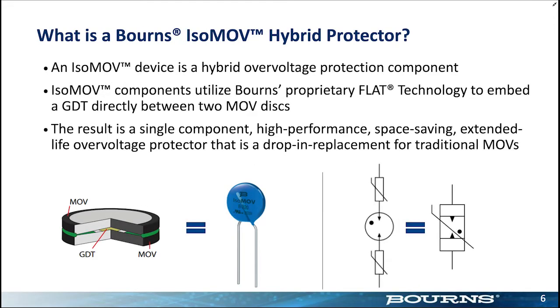So what is this IsoMOV? It's called a hybrid protector because it contains components of both the GDT and an MOV in it. We've taken our flat GDT technology, right? A normal GDT is about the size of the last index of your little finger, and we're able to squish that down, be very thin, and we use the technology that we've learned from doing that in designing this MOV. You can see I've got 2 MOV discs on the top and bottom with the GDT stuck in the middle. And it looks just like an MOV. You can take an existing MOV out of your circuit and plop this guy down and immediately get an improvement, right? There's no redesign of the PC board or anything.